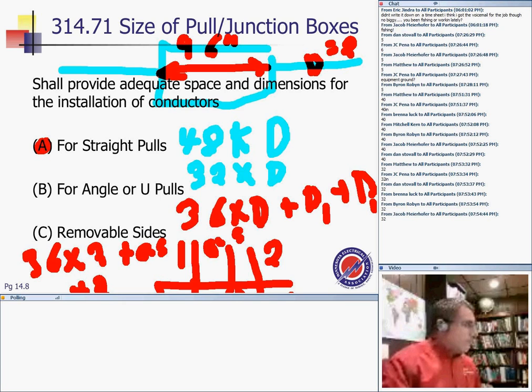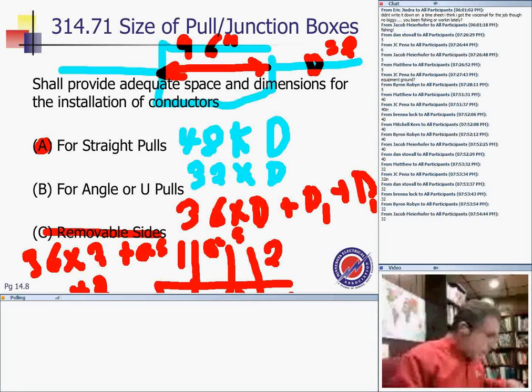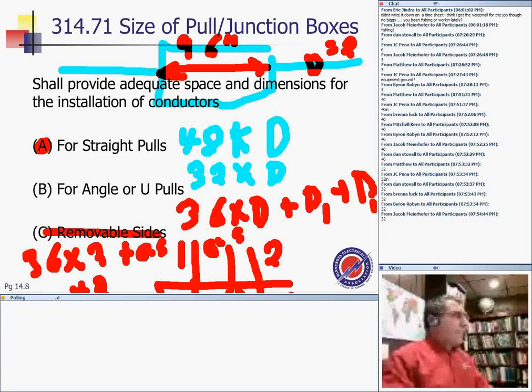Any questions about this? It's interesting how they do it. For conductors entering in a removable cover, you can go by the dimension based on 334. Provide bending for the conductors as provided in 334. That is the table you go to in 334 to find the bending radius for medium voltage. And for the straight pull, you guys have probably never seen the 48 and 32. I multiply the diameter of the cable.